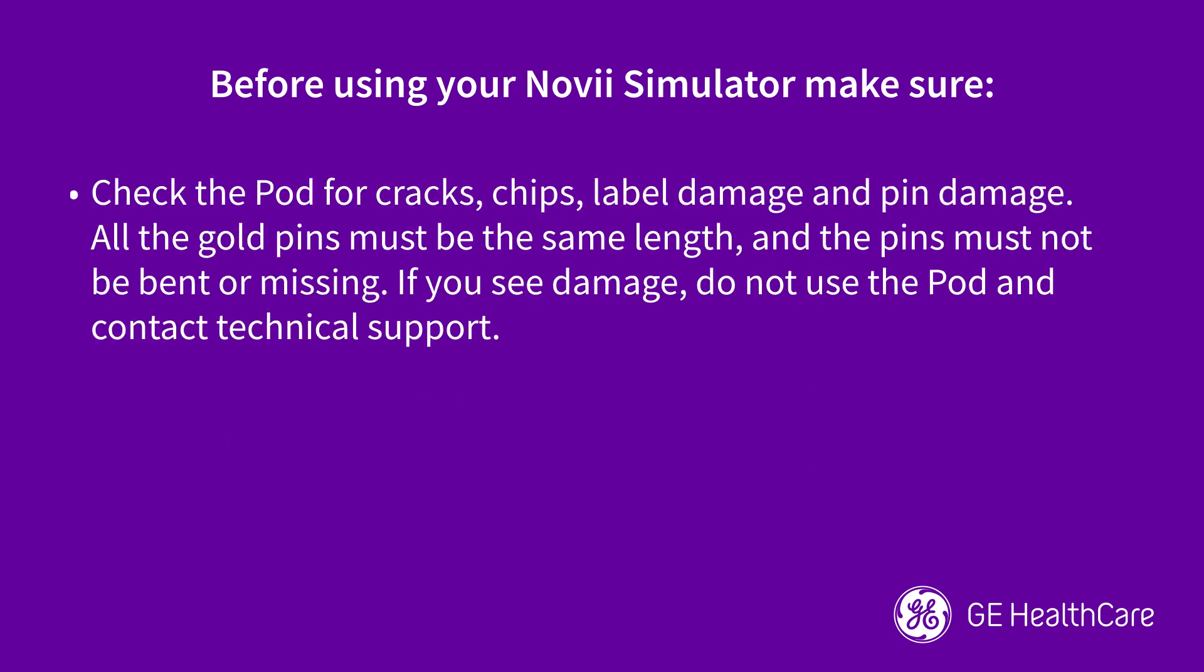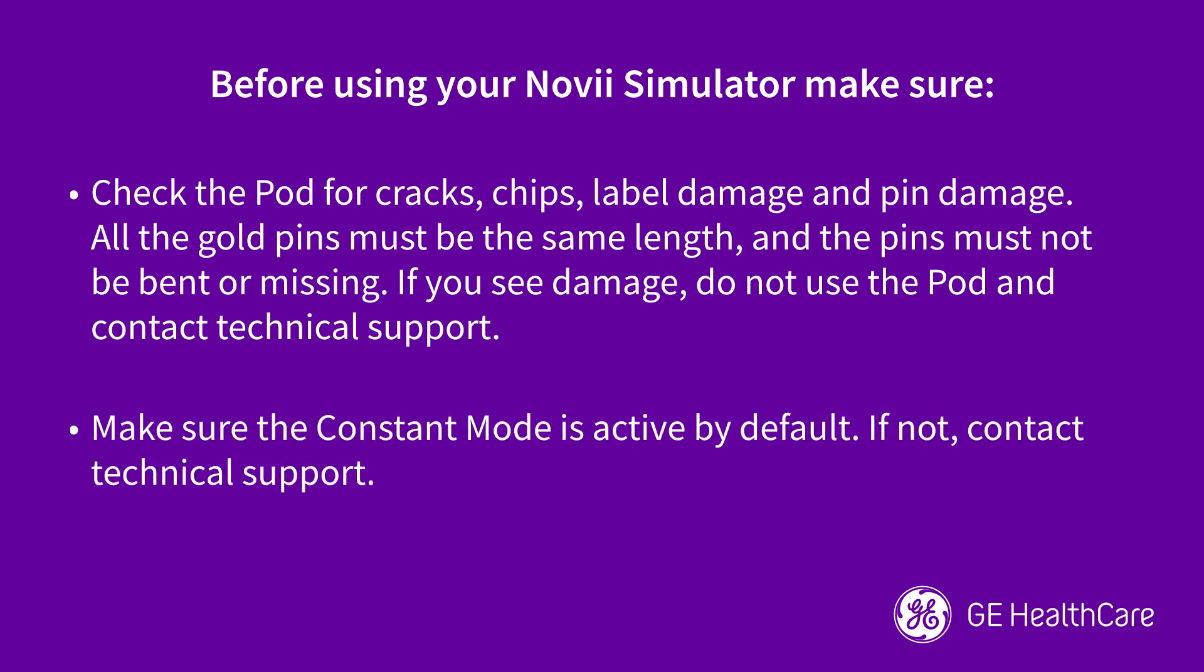Make sure the Novii wireless patch system and the Corometrics 259CX or 174 are installed. Check the pod for cracks, chips, label damage, and pin damage. All the gold pins must be the same length, and the pins must not be bent or missing. If you see damage, do not use the pod and contact technical support.